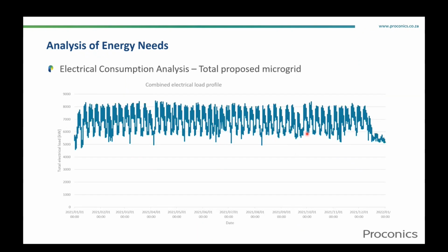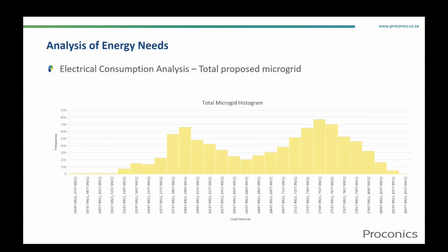When you take both customers together in one microgrid, this is what the profile looks like - the variation is a lot less as a percentage. The total maximum demand is about 8,500 kilowatts, and the combined load factor is 81%, resulting in much better utilization of the electrical infrastructure than with customer 2 alone. Here's the histogram for the entire microgrid load.